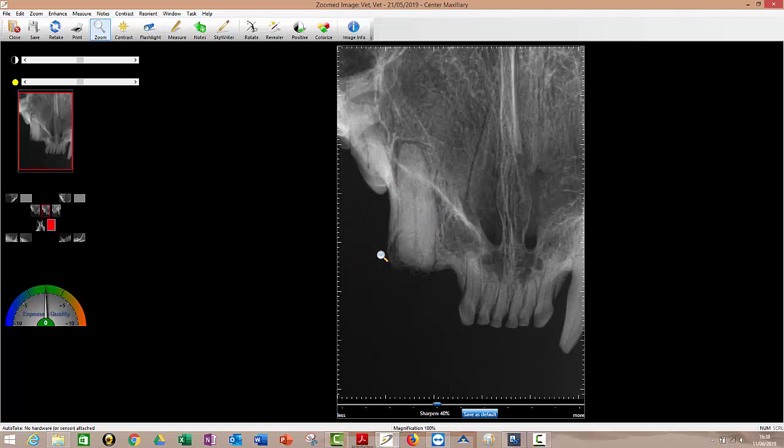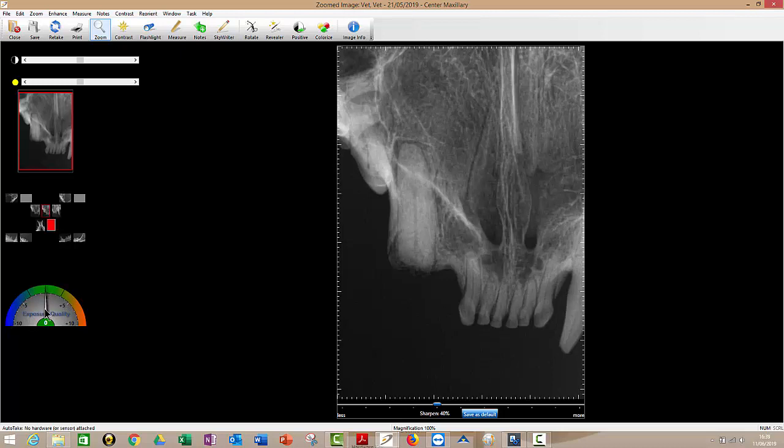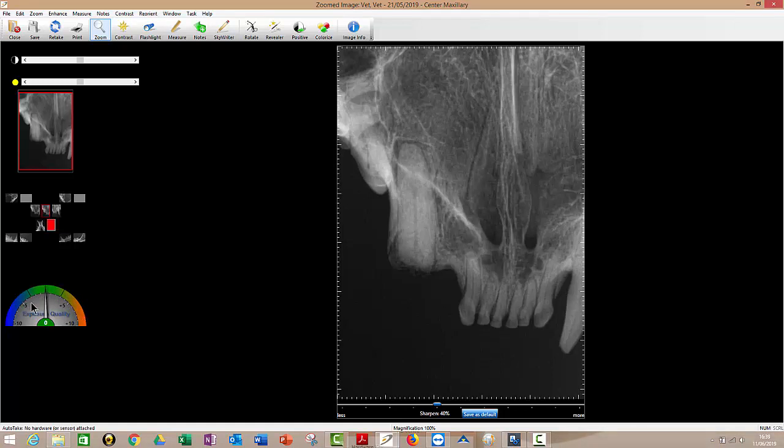So just to take you over what you're seeing here. This is obviously your zoomed image of your radiograph. You've got a sort of preview of your series here. This here tells you whether or not you exposed the image correctly. Obviously, after the event, you know, you've taken the image, but it just gives you an indication of if this needle was consistently over here, I'd be having very wishy washy images and they'd all be underexposed. If the needle was over here, my images would be overexposed and very dark looking. So the goal is to try and get the needle as close to zero as you can to get a properly exposed image.